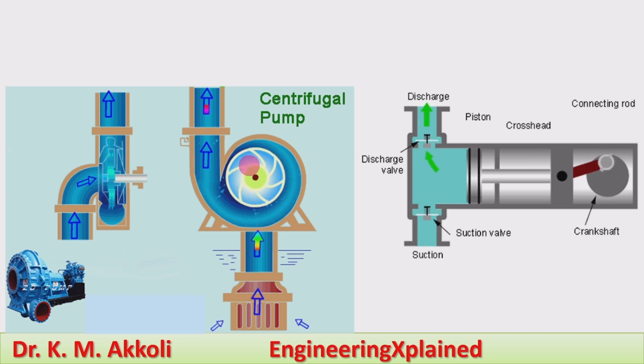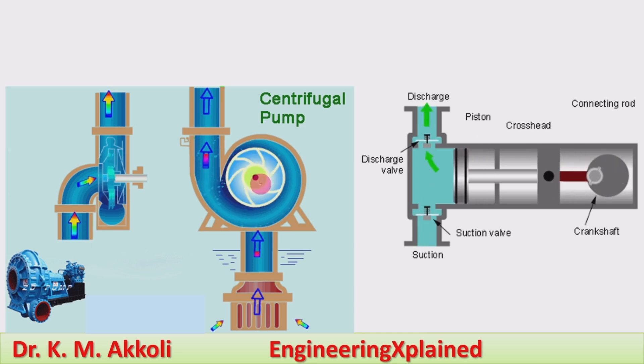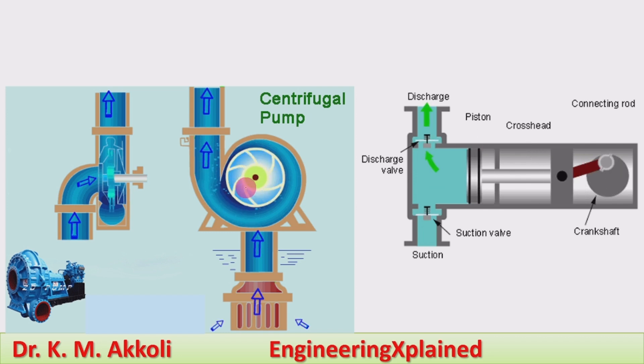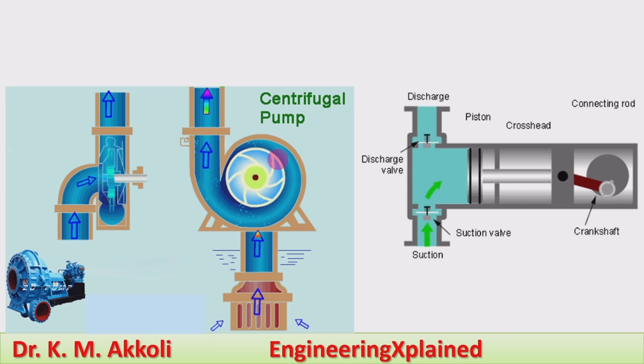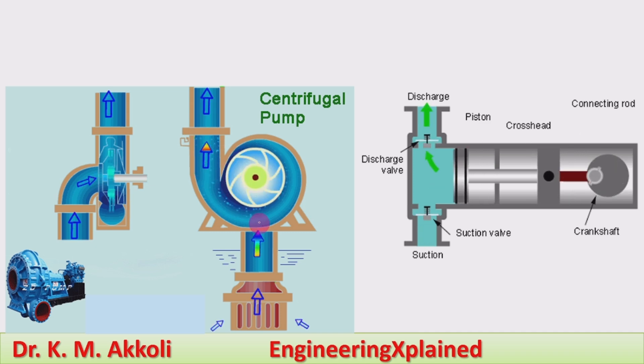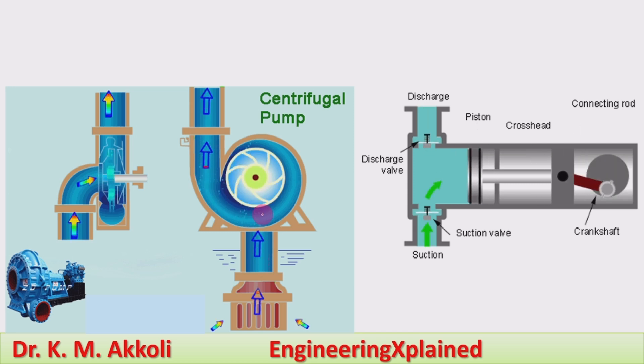When the impeller starts rotating, it rotates the fluid along with it by means of its blades. Due to that, centrifugal force acts on the fluid — centrifugal force is the outward force acting on the fluid during its rotation. Due to that centrifugal force, the fluid is pressurized in the delivery line. As the fluid in the casing is pressurized and flows in the delivery line, a partial vacuum is created inside the casing, causing fluid to flow in from the inlet.